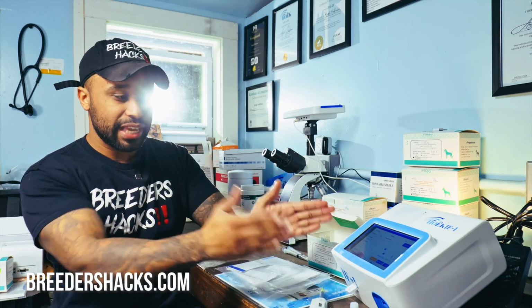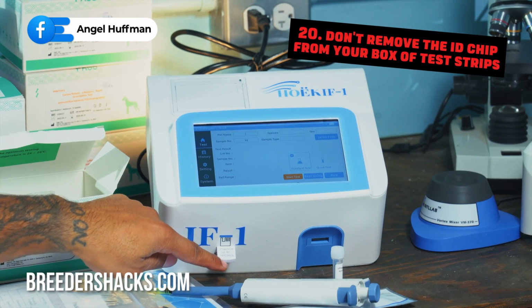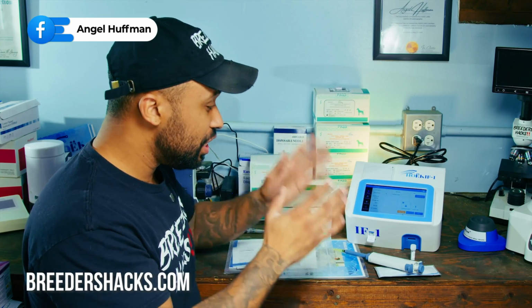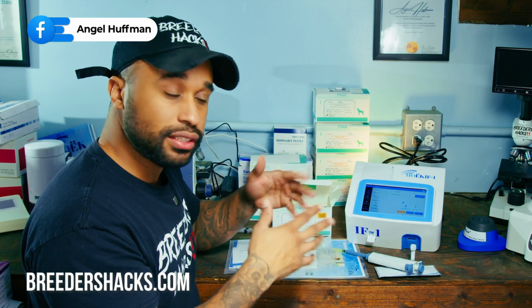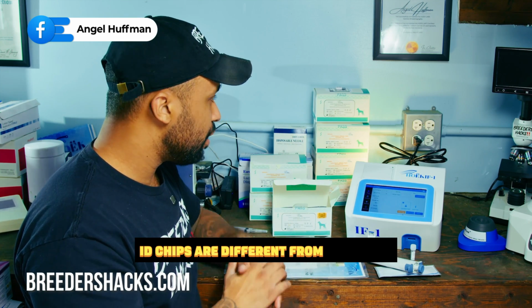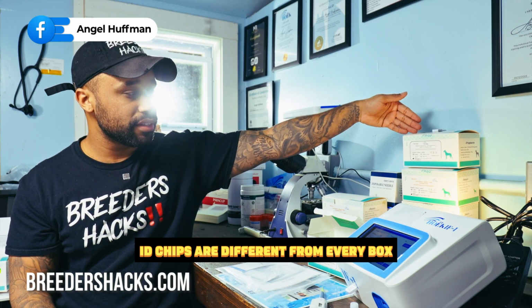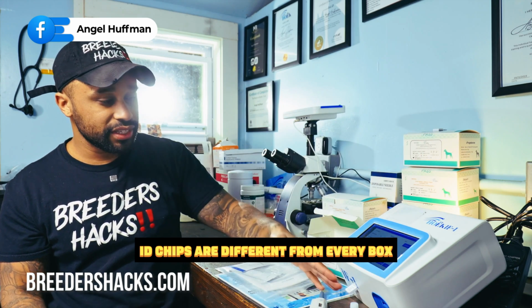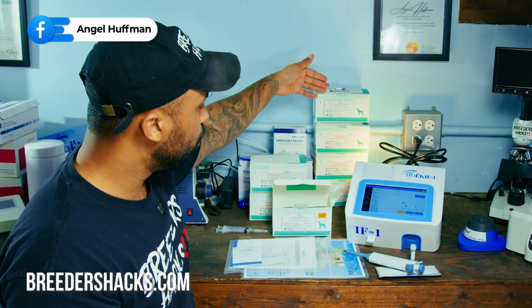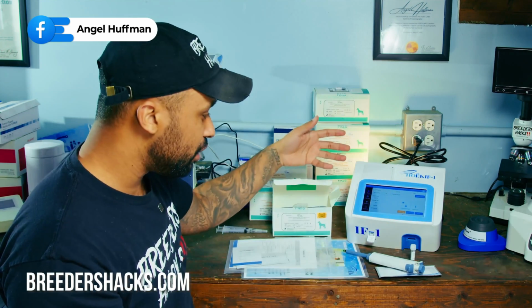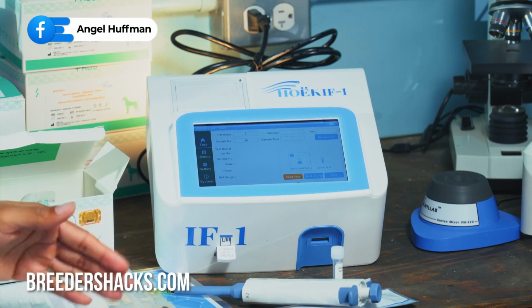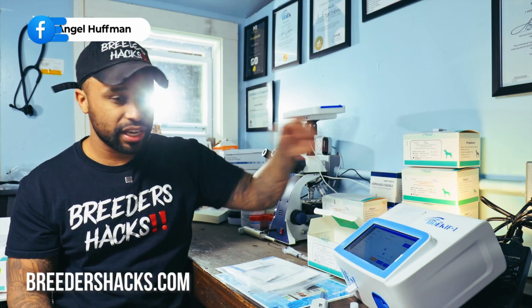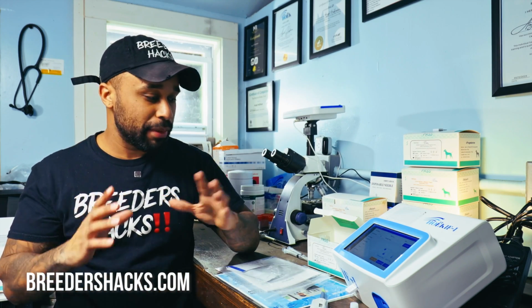So now the machine is calibrated to this box of test strips. When you have your test strips, don't remove the ID chip from your box, because each ID chip is usually different to every box. You don't want to lose it, because if you use a test strip from this box or that box with the wrong ID chip, say you lose it or misplace it or throw everything together in one bin, now the machine isn't going to work with this ID chip for these test strips. So that's something to keep super in mind. Keep everything that comes with your test inside its box, including the ID chip.